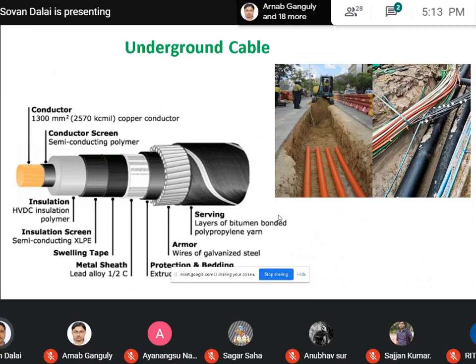But in the case of the underground cable, this is the actual core of the cable, or you can say the conductor where the high voltage is connected, and the outer portion is called the armor, which is connected to the ground. In between this high voltage core and the armor or the ground, there are different layers of insulator. Each insulator layer has a different function. Some of the insulators provide only insulation, some are semiconducting. Here you see some of the insulating layers are semiconducting. XLPE stands for cross-linked polyethylene. So there are different types of layers of insulation.